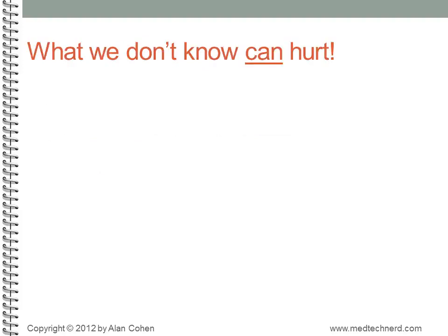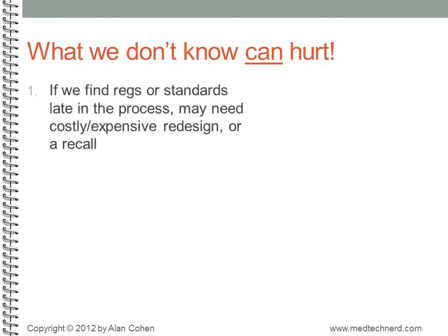Many companies, particularly inexperienced ones, start thinking comprehensively about regulations and standards late in the game. This is a bad idea. It's important to think about these things in a thorough, comprehensive way up front for a couple of reasons. First off, if we find out about a regulation or standard late in the game, we may have to go back and perform redesign that costs money and delays product launch, or even leads to a recall. If you think about it, failure to meet a regulation is really a bug, since it prevents the product from meeting its intended use.